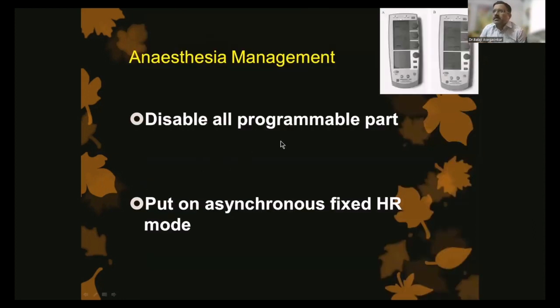As far as anesthesia management is concerned, one rule is very important: always disable all programmable parts, because these sophisticated programs depend on so many inputs from the heart. During anesthesia, with the use of cautery or even shivering, there are so many parameters which can give a false sense, a false sensing to the pacemaker. So disable all programmable parts of the pacemaker, then put the pacemaker on asynchronous fixed heart rate mode.